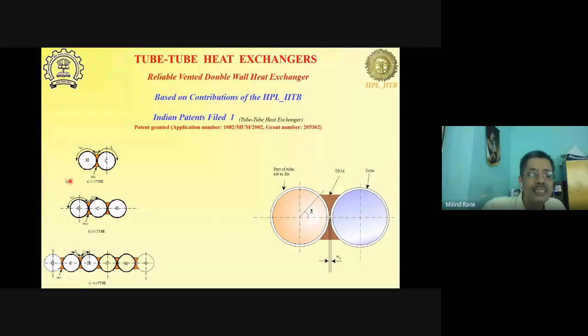You can have two tubes side by side. If you have a gas exchanging heat with water, you can have two gas side passages because the density is low, the specific heat is low, and the heat transfer coefficient is low, so you need more surface area for the gas side. So all those flexibilities are built in. Now, just to give you some idea, we have done heat exchangers with 6 fluids exchanging heat with each other in a single heat exchanger and deployed it in industrial applications, and they have been working well.